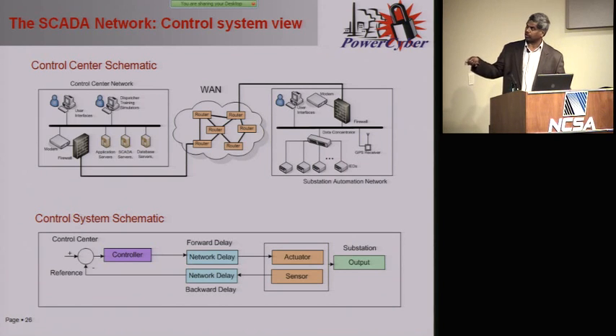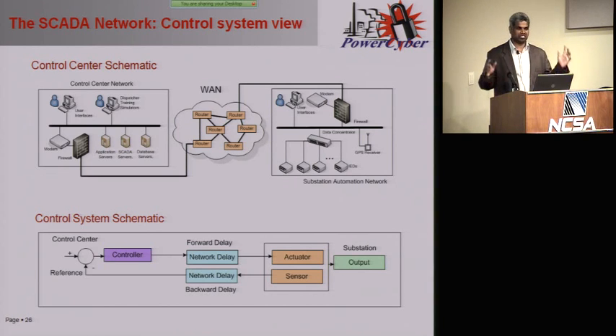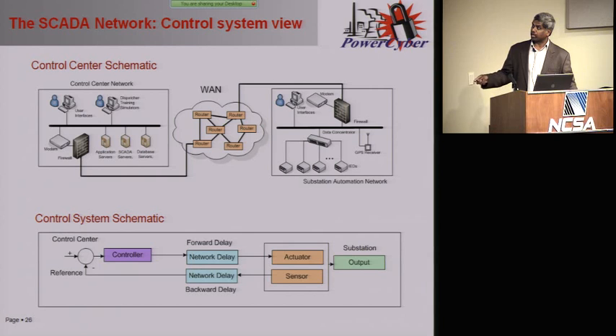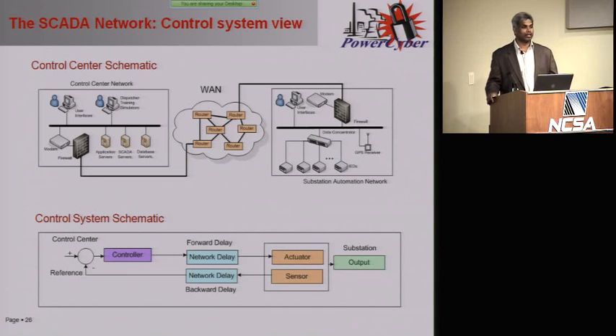You have a substation and a control center: data acquisition goes one way, decision making happens at the control center, then control goes back. Let's assume the substation is highly protected and secure, and similarly the control center is highly protected and secure. But even if the communication network is secure, one can create a huge flooding-based attack using honeypots or botnets, flooding the network and slowing down SCADA control communication, impacting the physical operation system.